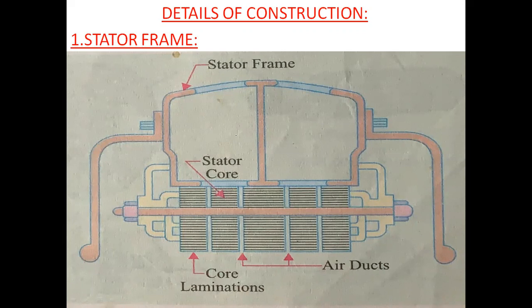Low speed alternators have a large diameter, and these have frames of large diameter, cast in sections for ease of manufacture. Second, ventilation is maintained with the help of holes which are cast in the frame itself. And the provision of radial ventilating spaces in the stampings provides air cooling of the machine.